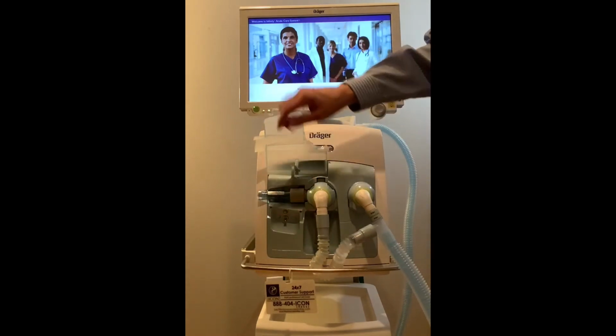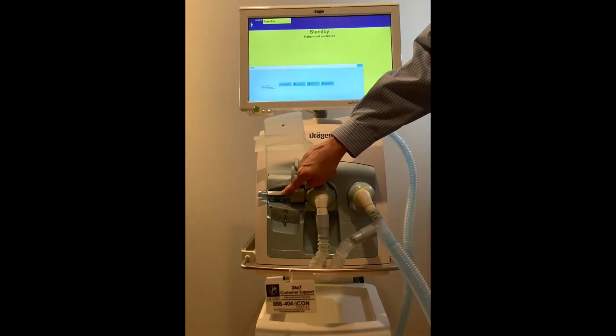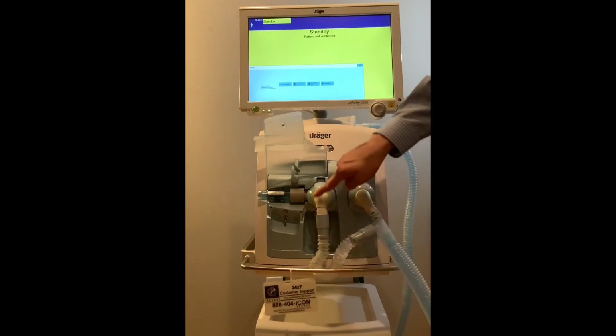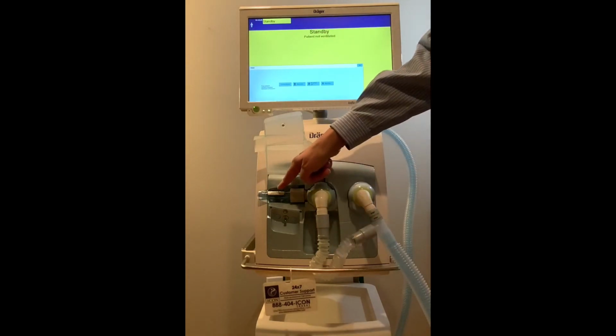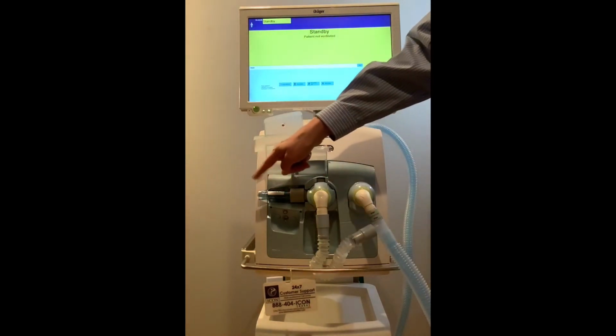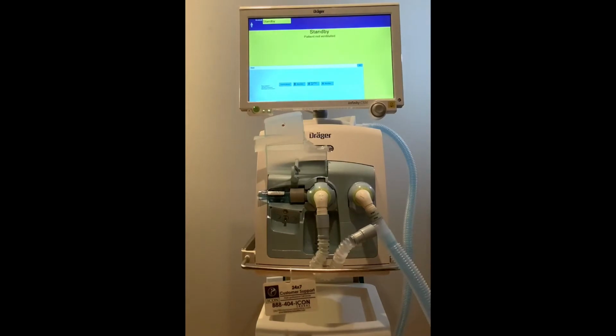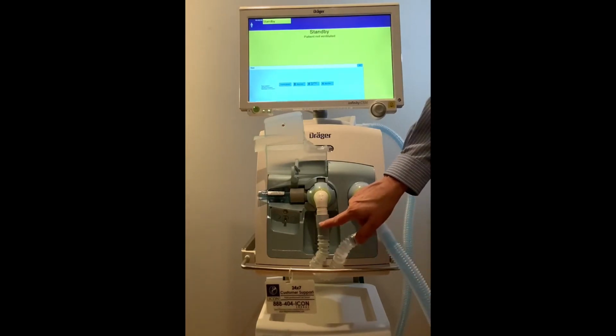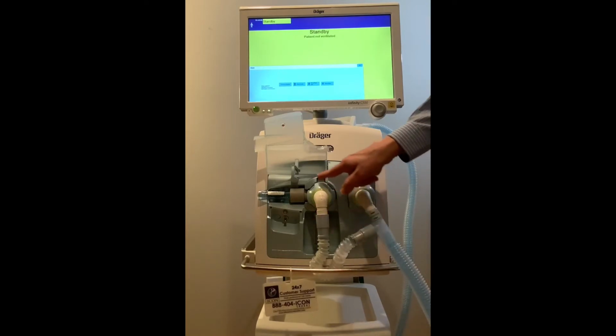If you lift the door, you'll find the expiratory flow sensor, and your gas flow goes through the expiratory valve to the expiratory flow sensor and out to the atmosphere. If you're going to be putting a filter in line, the filter would go between the ventilator circuit and the expiratory valve. No gas that flows through this system goes into the ventilator box itself.